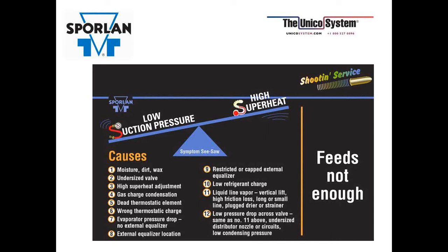It could be a dead element. If you have a dead element, you just take the bulb off the line and hold it in your hand, and the warmth of your hand should be enough to open the valve up, and that's the first indication if it's a dead element or not. Since that's your opening force, if you don't have any constituents in your bulb, then you have no opening force, and you're going to be in that low suction pressure, high superheat condition.